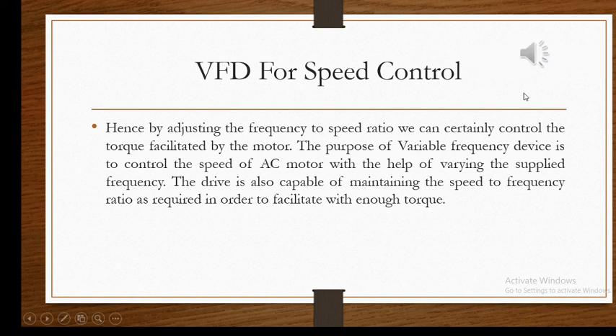We know that in the case of an induction motor, the torque is directly proportional to the flux in the air gap, which is directly proportional to the ratio between the voltage and frequency. Hence, by adjusting the voltage to frequency ratio, we can certainly control the torque facilitated by the motor. The purpose of a variable frequency drive is to control the speed of an AC motor by varying the supplied frequency. The drive is also capable of maintaining the voltage to frequency ratio as required in order to provide enough torque.